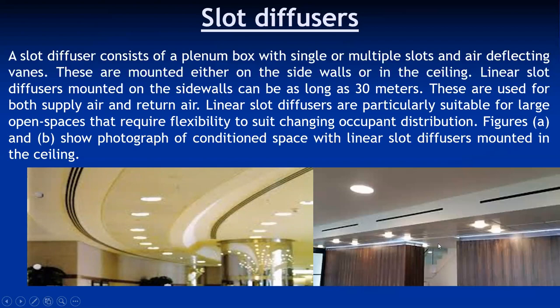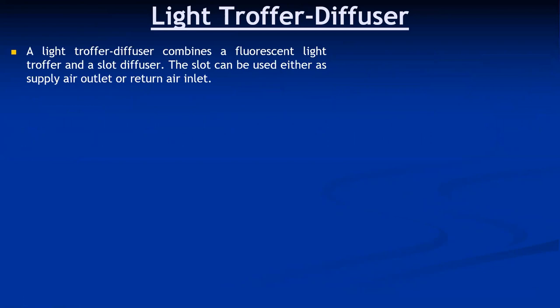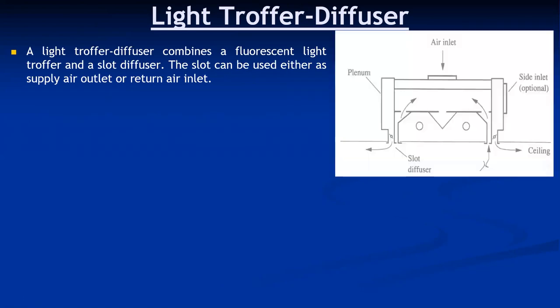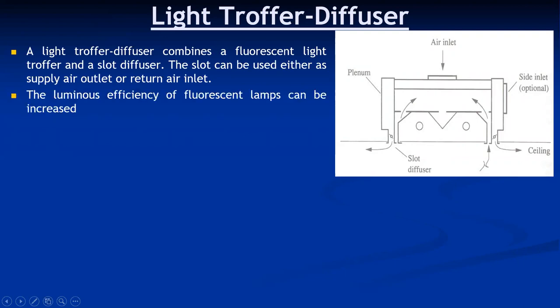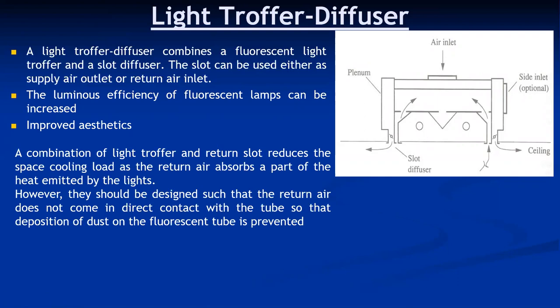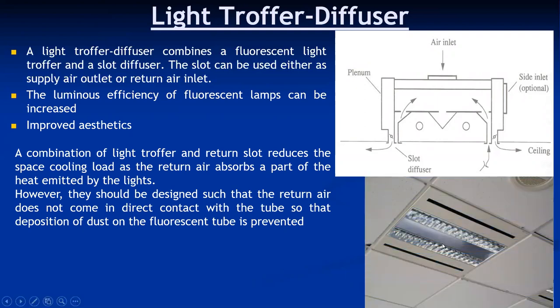One special type of diffuser is called the light troffer diffuser. A light troffer diffuser combines a fluorescent light troffer and a slot diffuser. The slot can be used either as a supply air outlet or return air inlet. Fluorescent lamps are located within the unit, and air flows through these slots — it may be return air or supply air. Generally, it is suitable for return air.